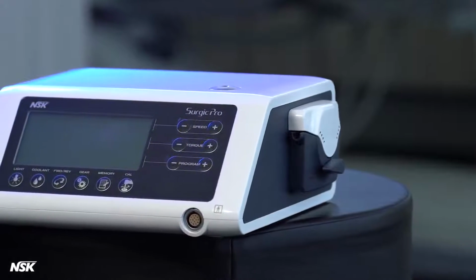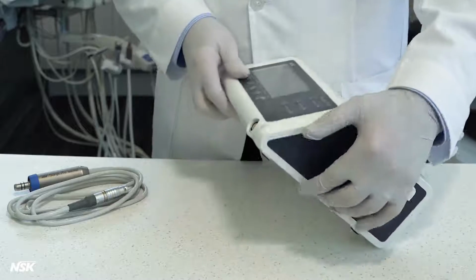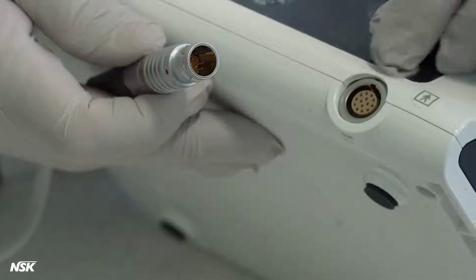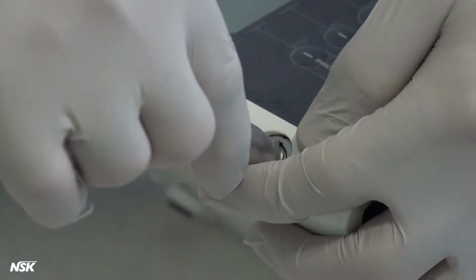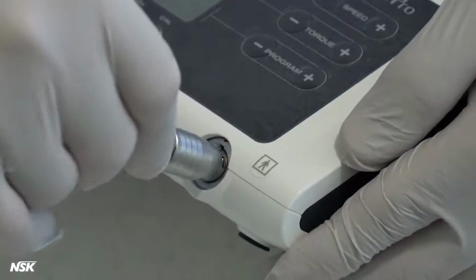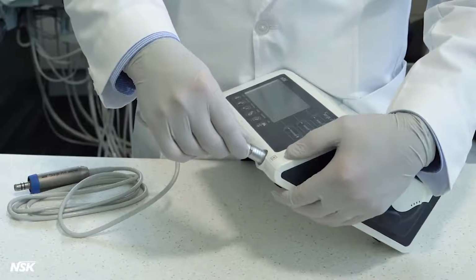Now let's move on to setting up your Surgic Pro. Installation. Connect the motor cord by aligning the marks on the cord connector and the connection on the control unit. Push in the connector until you hear a click. Slightly pull the cord to make sure it's locked in place.